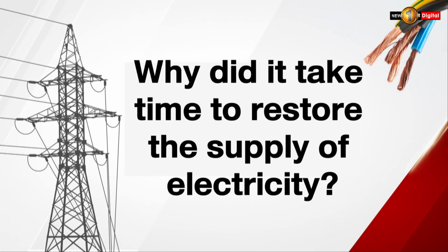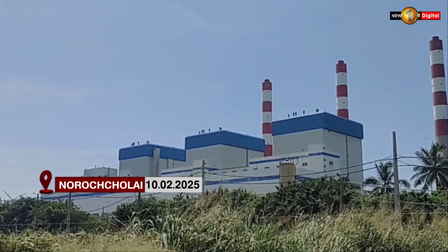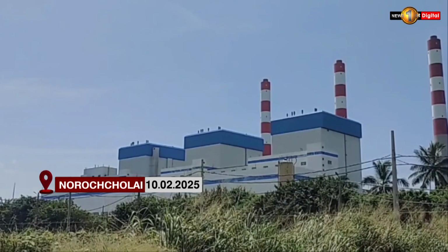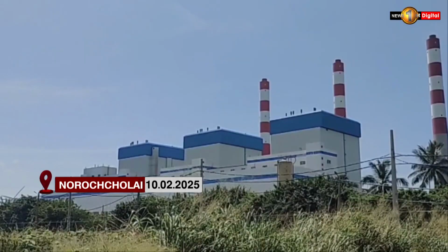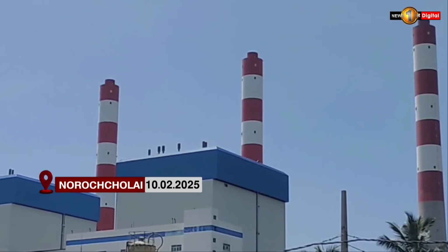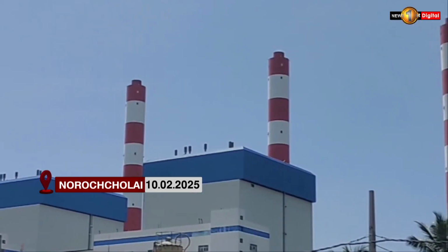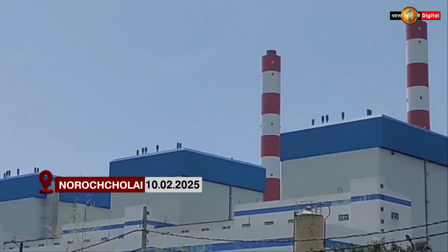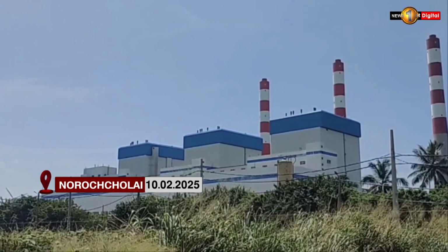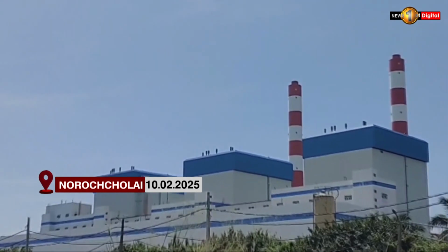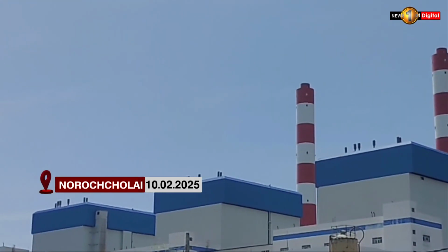Why did it take time to restore the supply of electricity? After the incident, it took time to restore power because the Norochcholai power plant, which produces continuous power, cannot be restarted instantly. Following the incident in Panadura, the sudden breakdown caused all 3 generators to go offline. Restoring power required relying on hydro and thermal power plants, which took several hours.